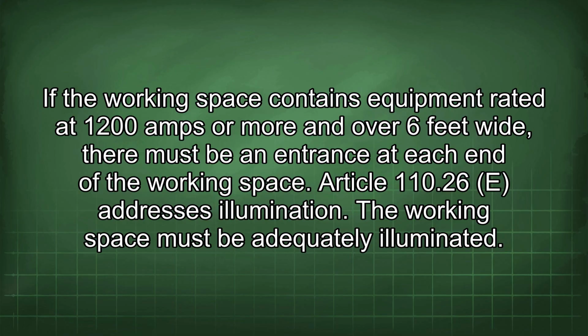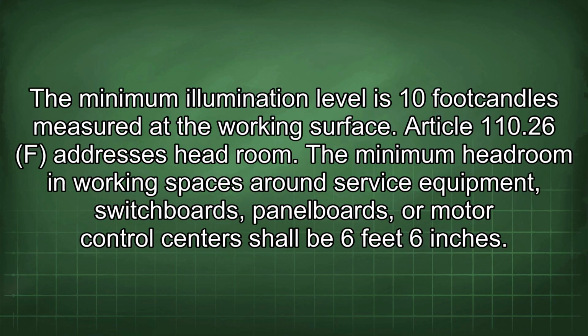Article 110.26e addresses illumination. The working space must be adequately illuminated. The minimum illumination level is 10-foot candles measured at the working surface. Article 110.26f addresses headroom. The minimum headroom in working space around service equipment, switchboards, panel boards, or motor control centers shall be 6 feet 6 inches.